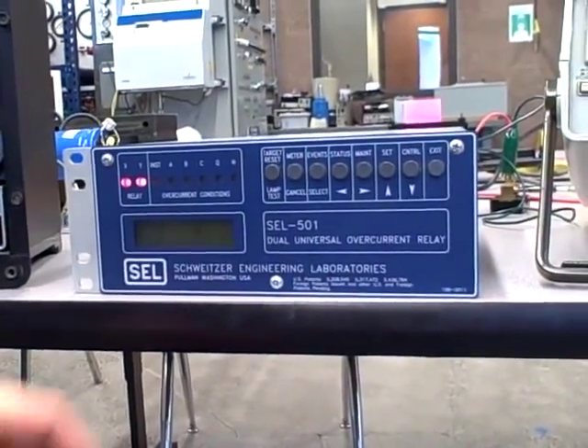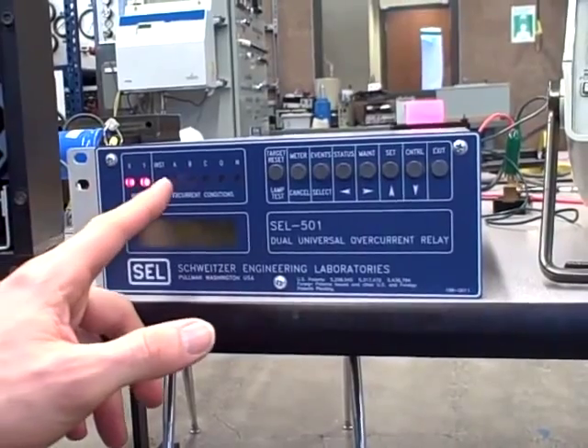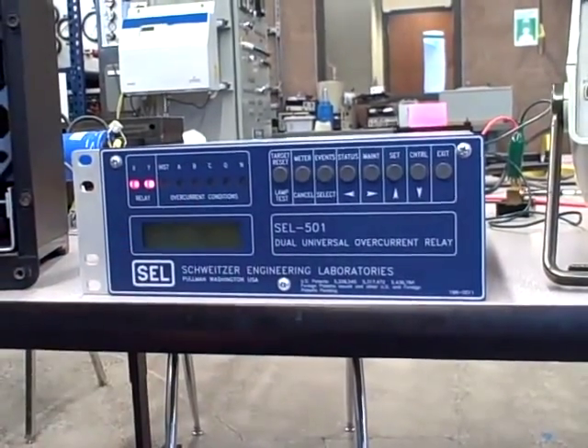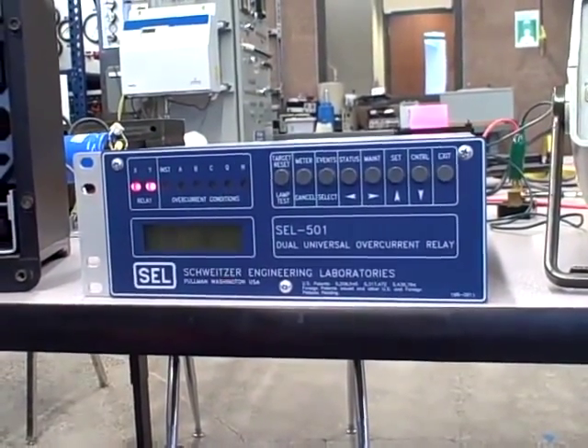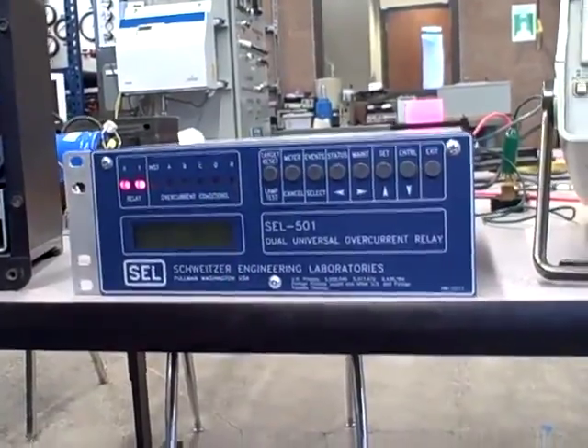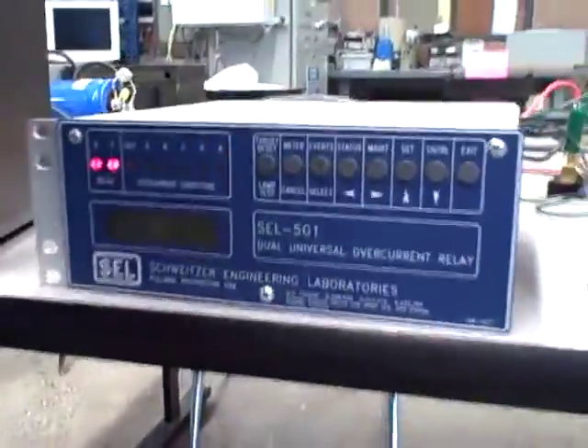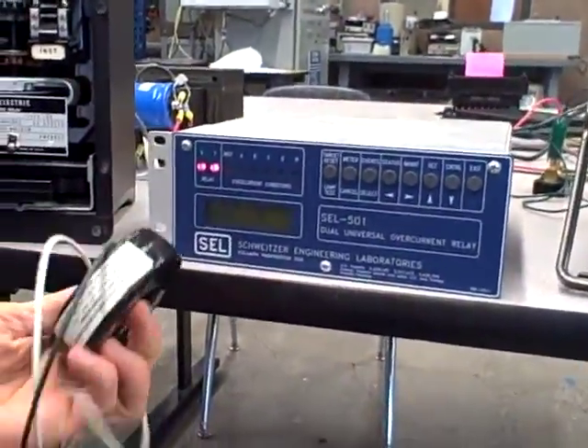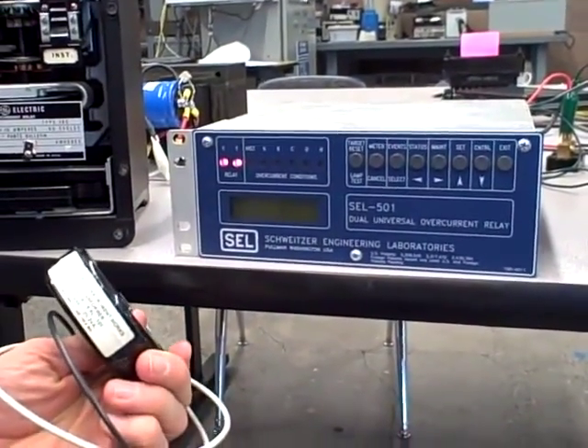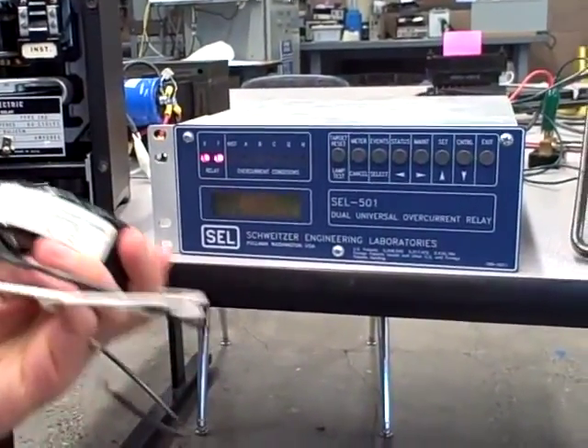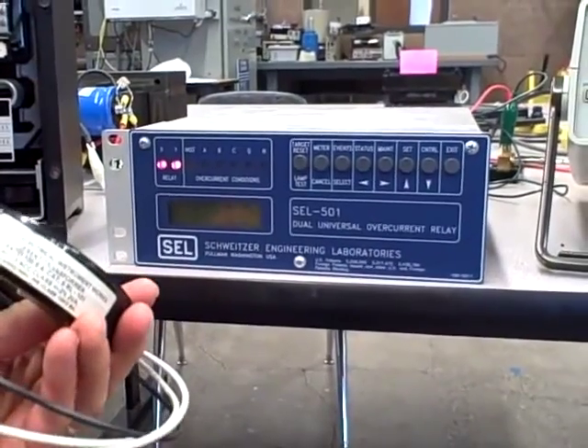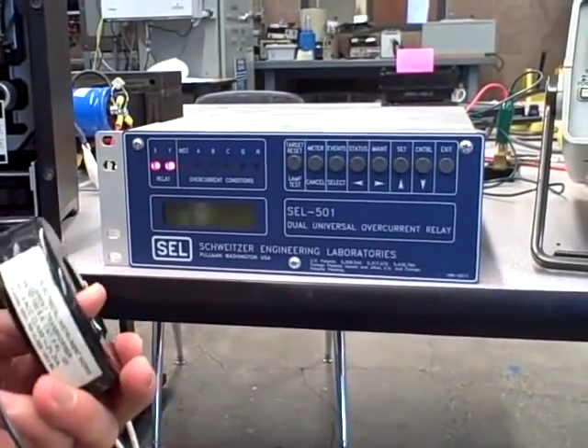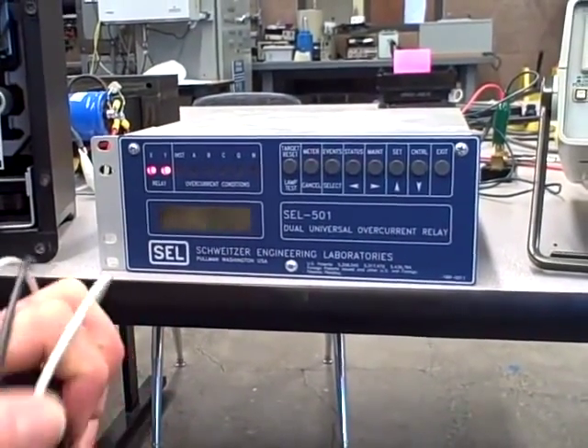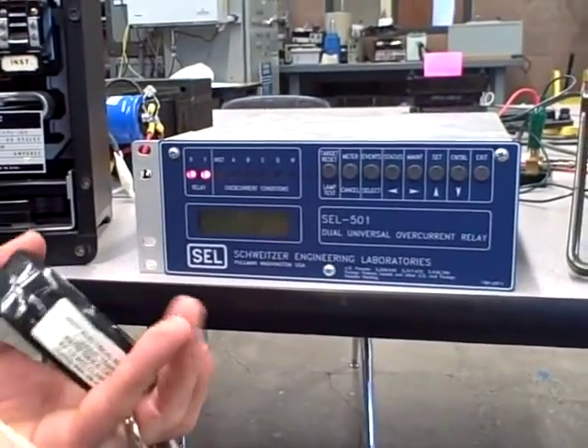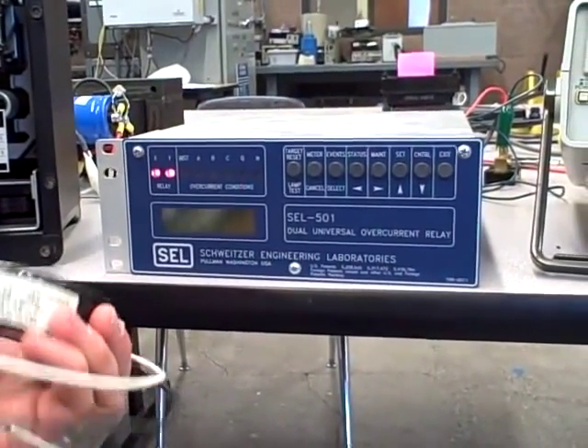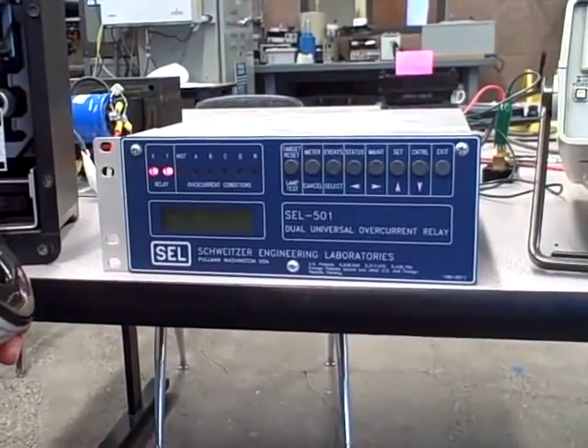In this particular case, we're going to be testing the X relay on phase A. Now to do this, I need to inject a certain amount of current into it to simulate overcurrent condition. Now as we recall, the current came from current transformers. This is the basic sensor device that would go around the power conductor, and when in this case you had 100 amps of current going through the power line, you would get 5 amps of current through the secondary wires of the current transformer, and that 5 amp signal will come down to the relay to activate it.